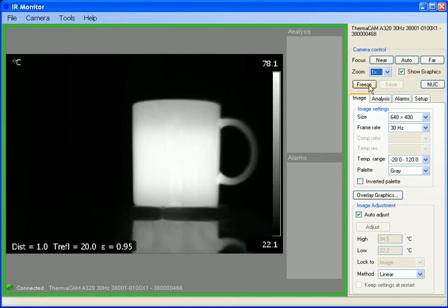save it for later. The NUC button stands for non-uniformity correction, and basically that's that paddle that clicks in the camera every once in a while. The paddle helps maintain uniformity across all the pixels, and when you first power it on, it'll drop quite a bit as the camera stabilizes in temperature. This also will happen every few minutes, or if the ambient temperature of the camera varies a lot, and it helps keep the image crisp, clear, and accurate with regard to temperature measurement.